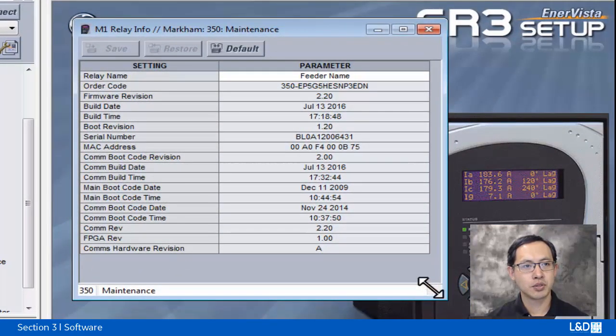And there is lots of information in this M1 relay info. And the most important 4 items, I would pick the relay name. That's configurable under the installation. And then, of course, the relay order code: what type of the relays, what are software options, what's the firmware, 2.2, are you using the latest one, so you can know from this firmware. And another one is the serial number. So serial number will be important if you have any problem with the relay, you want to contact the technical support, you need to provide the serial number of the relay.